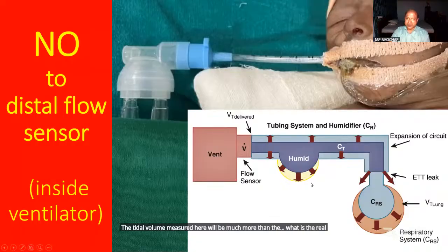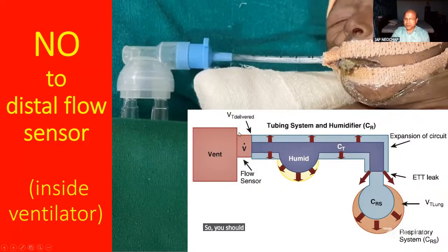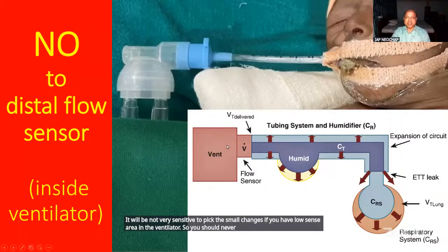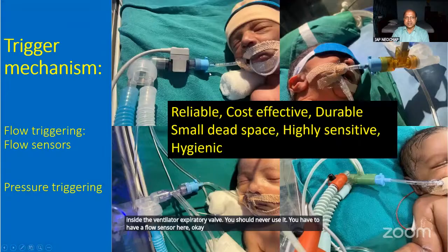So the tidal volume measured here will be much more than the real tidal volume. Also, it will not be very sensitive to pick up small changes if you have the flow sensor here in the ventilator. So you should never use a distal flow sensor, which is inside the ventilator expiratory valve. You should never use it. You have to have a flow sensor here.